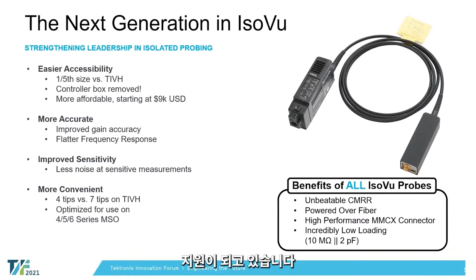So let's get into some of the tip changes. The architecture of the tip, as you might imagine, with the overall reduction in the size of the probe head, required a change in the tips that are designed for it. So our product line team did a great job in redesigning them, slimming them down, making them capable of fitting into smaller, tighter spaces. And to be able to do that, we've also scaled the dynamic range of the probe itself. So you'll see the two different colored bars there illustrate the different probe tips that were required to get to different differential voltage ranges. So we had 7 different tips that made the range capable of our Generation 1 IsoVu probe, capable of getting out to 2500 volts, or 2.5 kV.